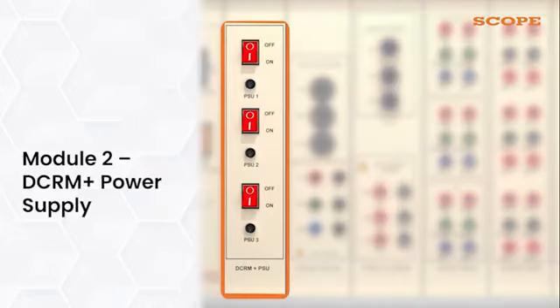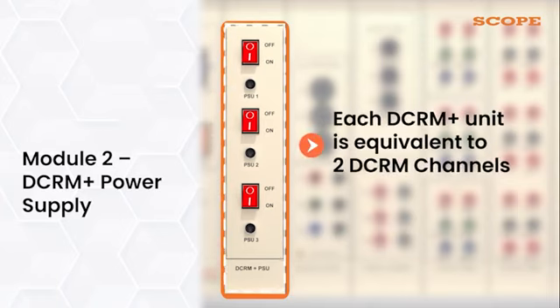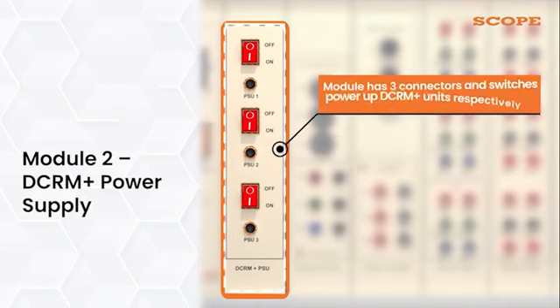Module 2. DCRM Plus Power Supply Module. Each DCRM Plus unit is equivalent to 2 DCRM channels. Thus, unlike its predecessor DCRM, which requires 6 channels DCRM for conducting tests. For simultaneous measurement of 3 poles with double break, you would require 3 DCRM Plus units. This module has 3 connectors and switches to power up 3 DCRM Plus units respectively.